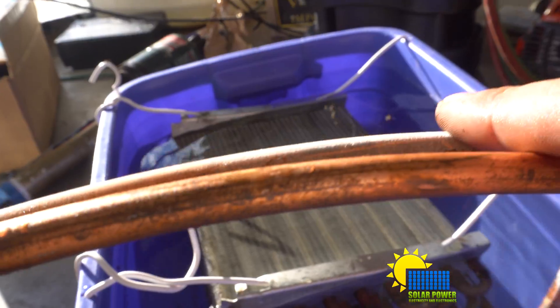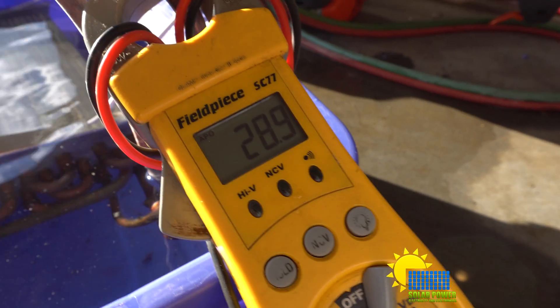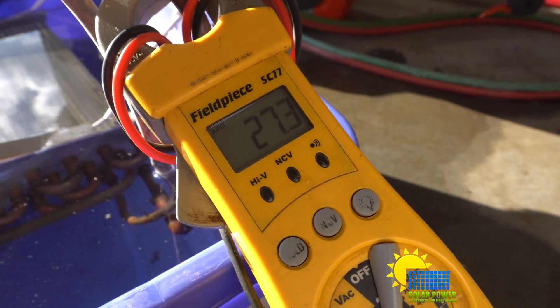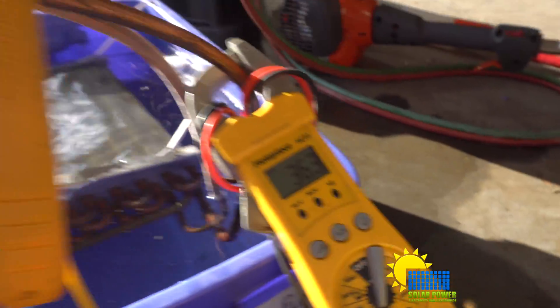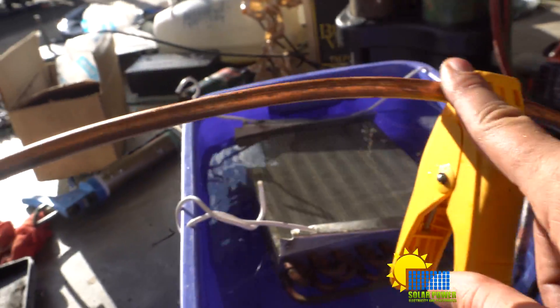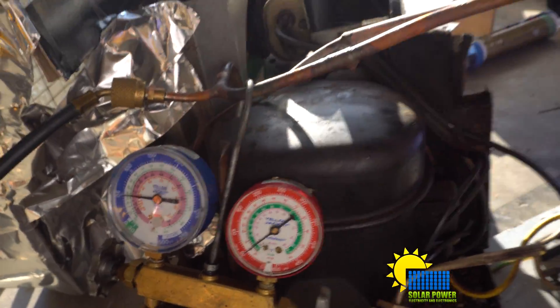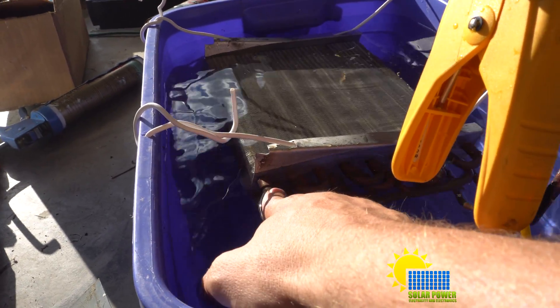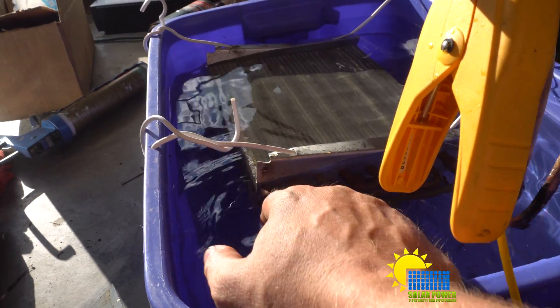The temperature on this other one is definitely colder — I'm going to check it. You can see it's 28... 27... 27. So it's 27 degrees on that one, and it is 44 degrees on this return line here — that's refrigerator temperature. Once this freezes up, it'll freeze up. It's freezing as we speak because it's so cold.